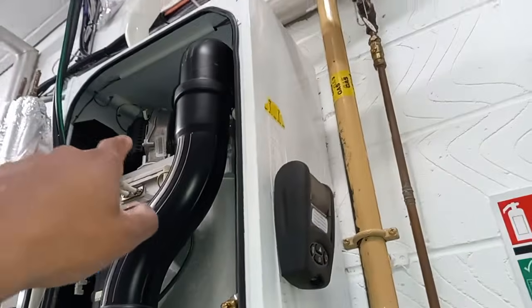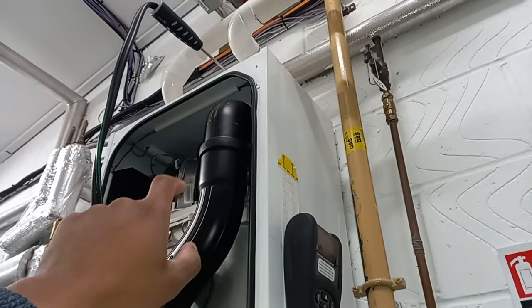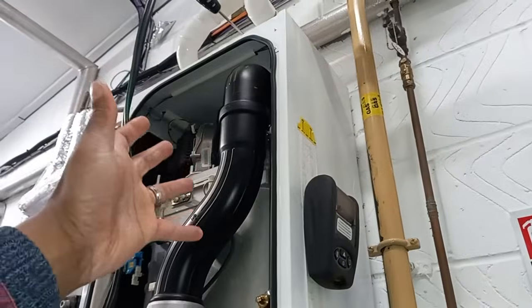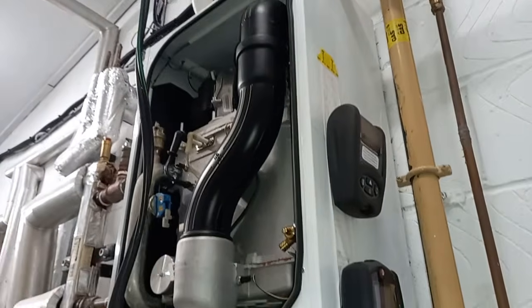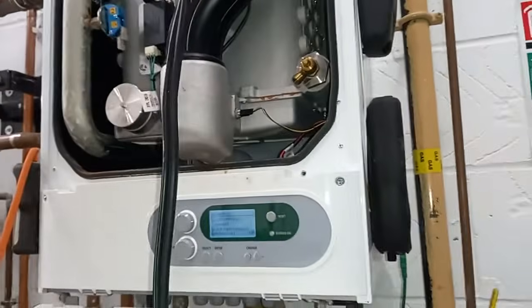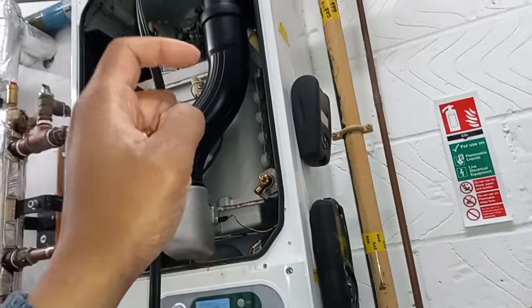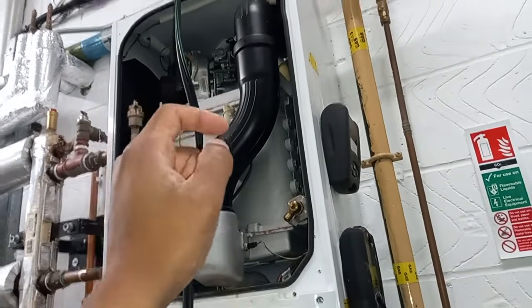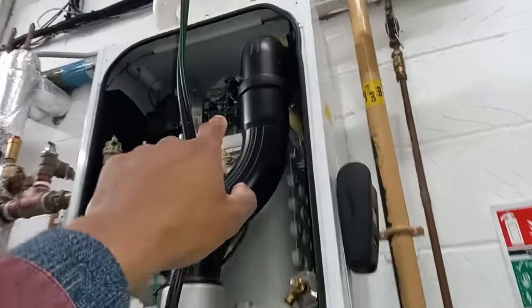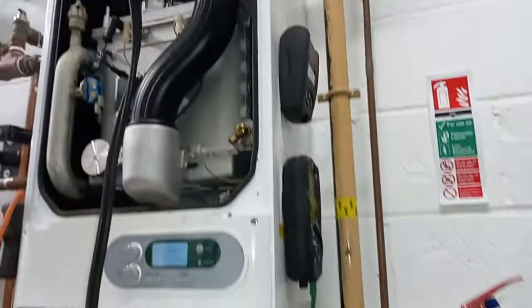Okay, back to the boiler. So we looked at our gas supply, we'll check in a moment how much gas it's pulling at high fire. That's important because we may not be able to carry out a gas rate, but in 9 out of 10 scenarios we want to check the working pressure up here on the boiler to see if our gas supply is adequate.